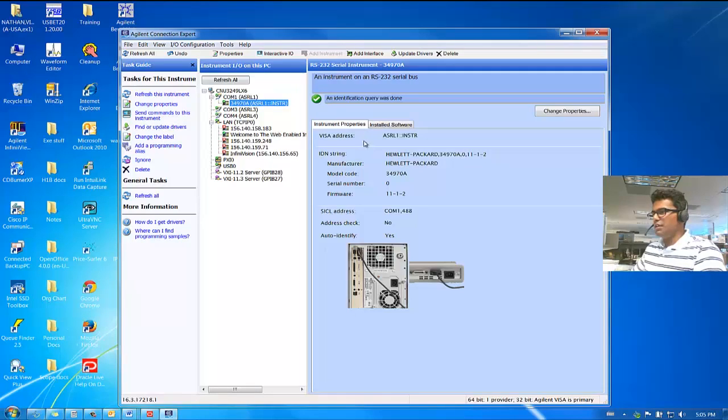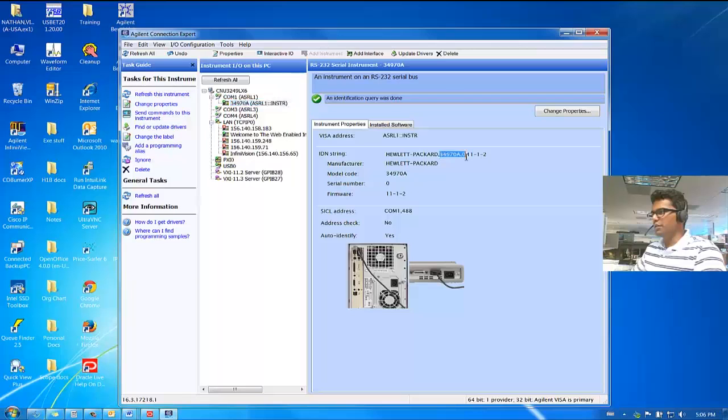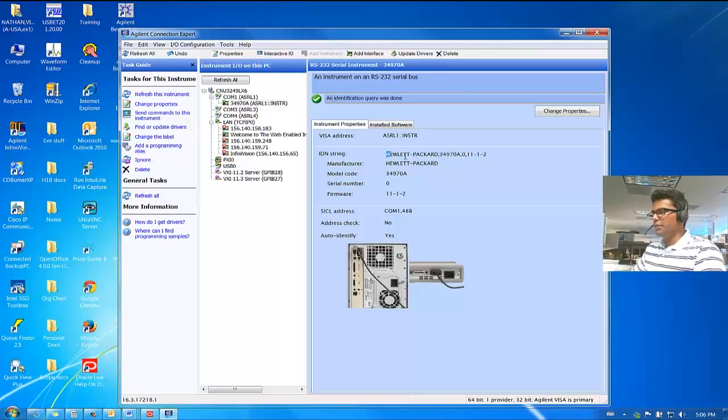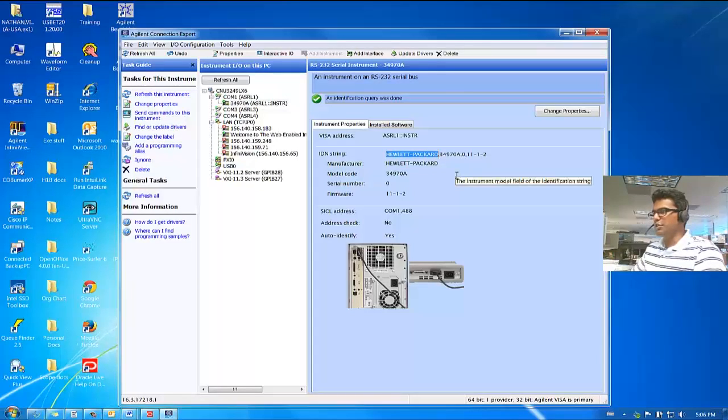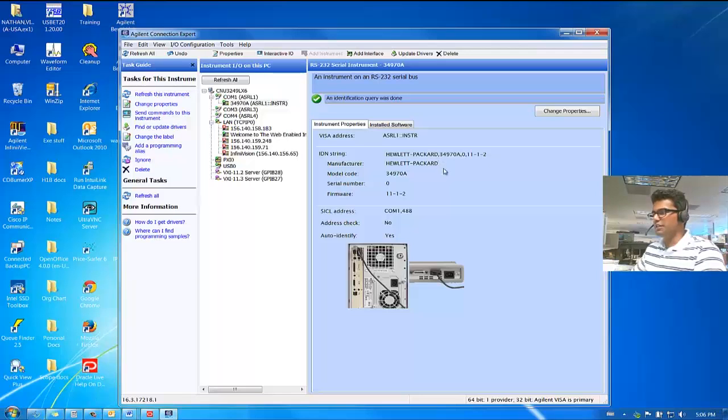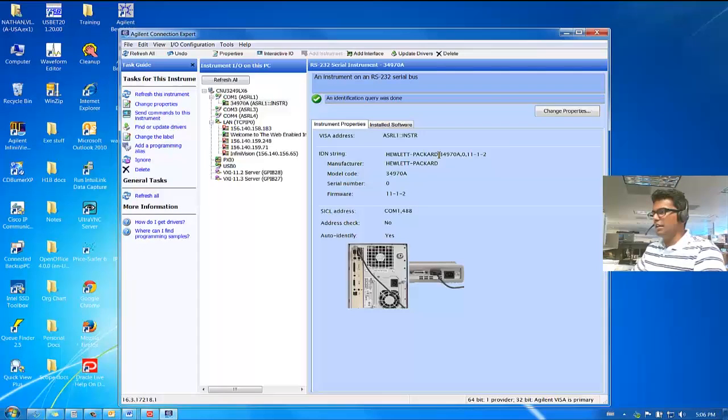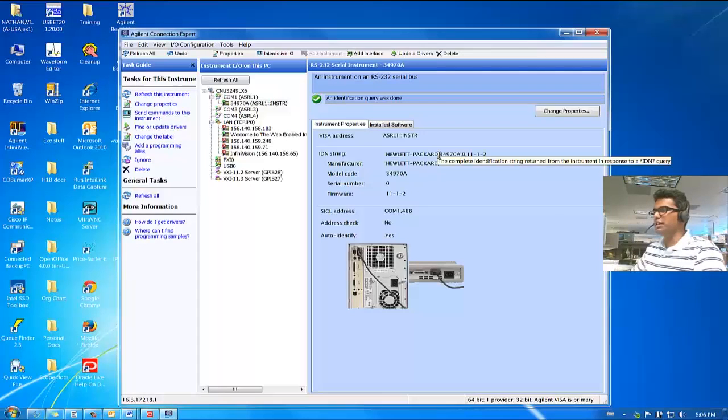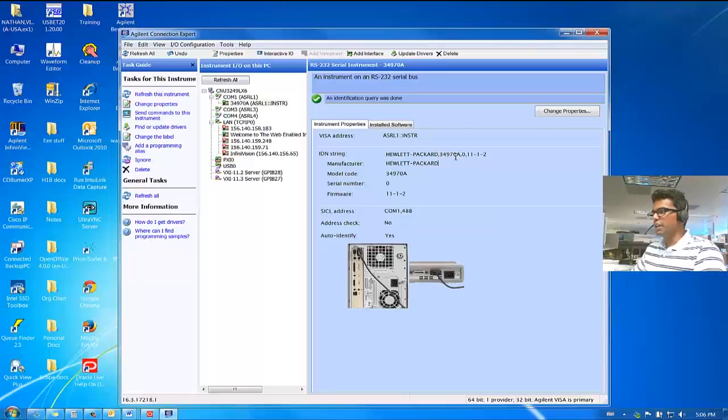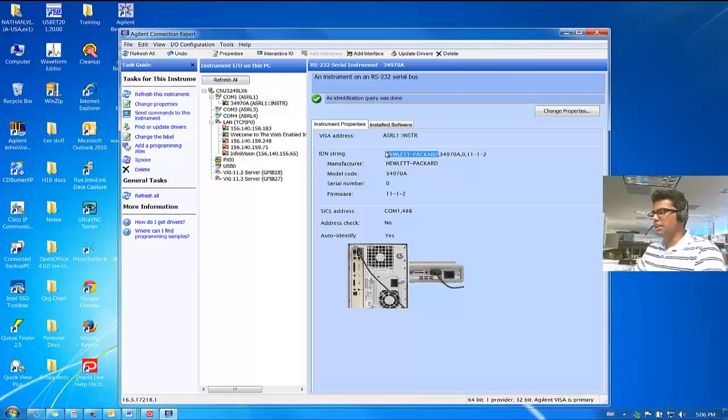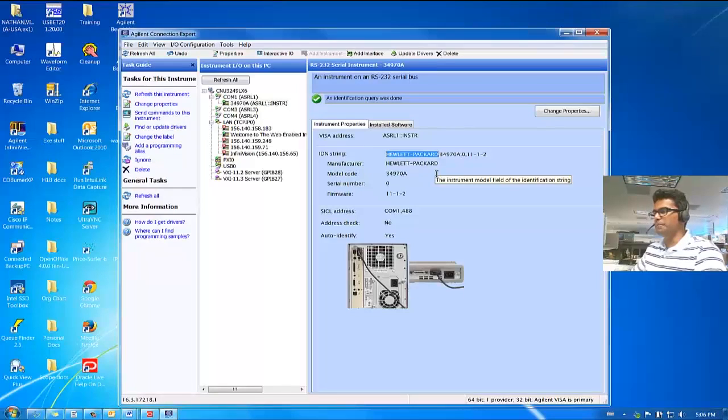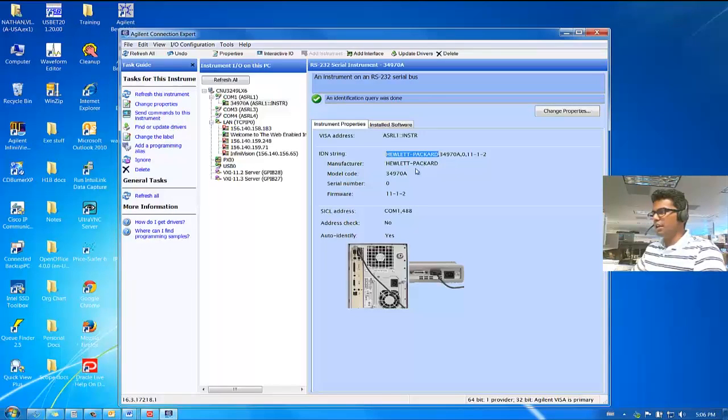And as you can see, it has already detected the instrument and is the right one. But if you notice, its name is Hewlett Packard. And this is because the instrument that I have has an old firmware on it. And back then, Agilent was under Hewlett Packard. If you had a newer 34970A, it will show Agilent over here.